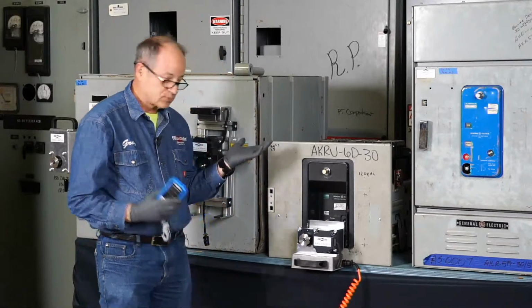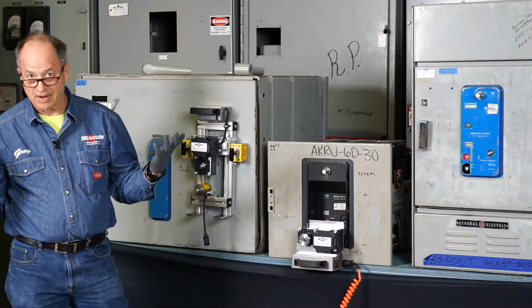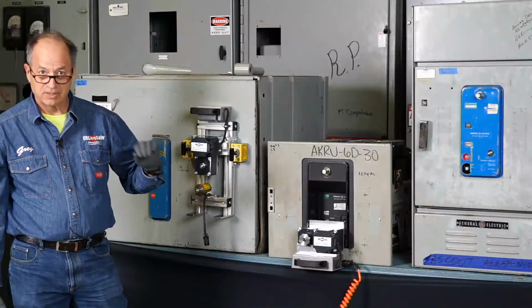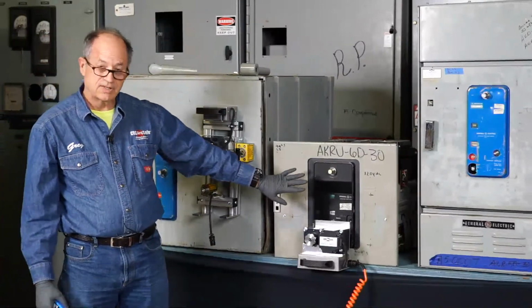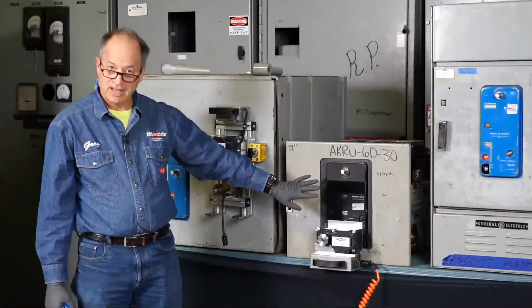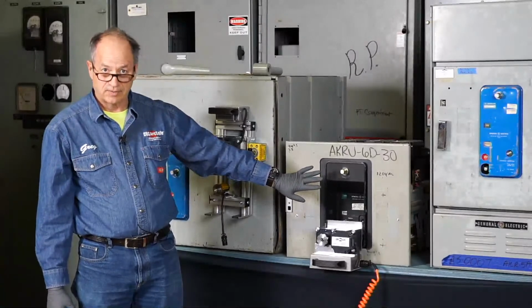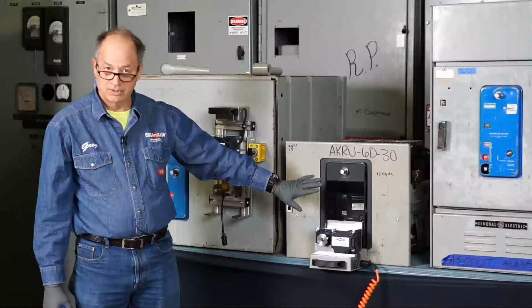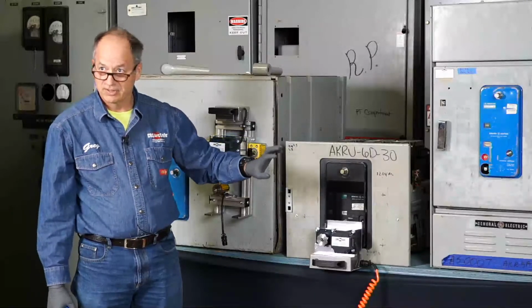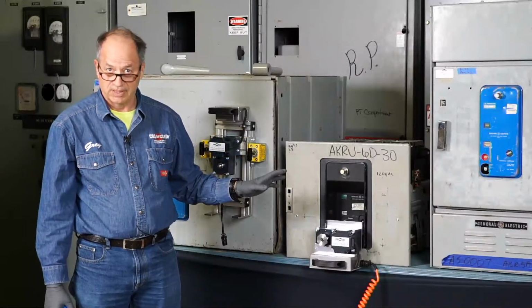Because we don't have it in a cubicle, it's not going to let us rack. So when you hear something like the clutch go off right there, that's actually what we would tell you: if that happens, check the circuit breaker and turn the system off so you're not imparting force into the racking system when you shouldn't be.